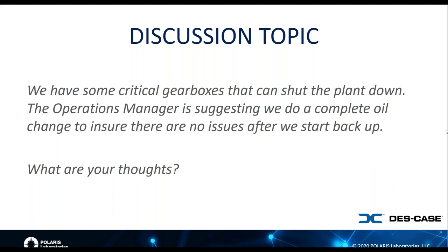The other thing I would add is as you bring gearboxes back up, as Hugo mentioned, you can have some degradation of the fluid. You can also have degradation of the gears and so on. And after that gearbox has been shut down for a while, that debris can settle out of the system. So it's not a bad idea, if you have a portable filtration system at hand, to plug it in as the gearbox comes back up to load and speed, to remove some of those contaminants so that when you're back up and under normal circumstances, the gearbox can continue to run. So if you don't have a permanently mounted filtration system on there, plugging in a portable system during startup can be a good help, particularly if it's a critical asset.